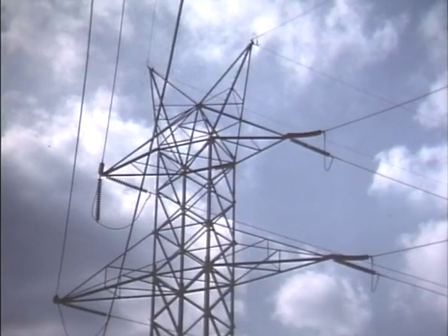In areas along the transmission line where there are sharp bends in the line or where conductors have been nicked or damaged, corona loss is at its greatest. This is because current tends to flow along smooth lines. Sharp bends or nicks create areas where power can be lost into the atmosphere. Linemen can minimize corona loss by ensuring that conductors are handled properly so that sharp bends and nicks are prevented.